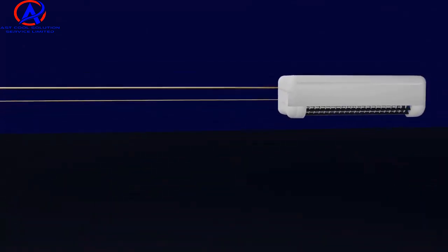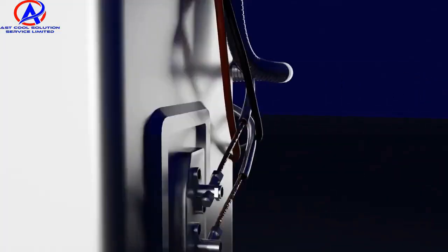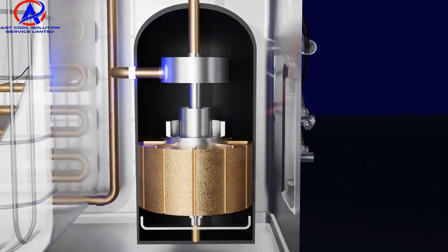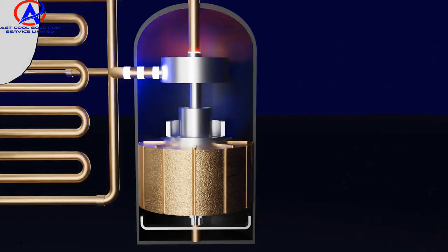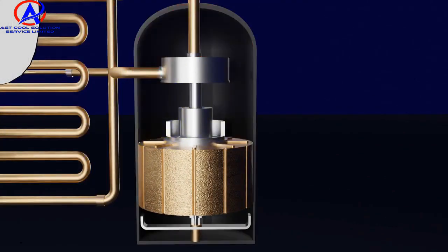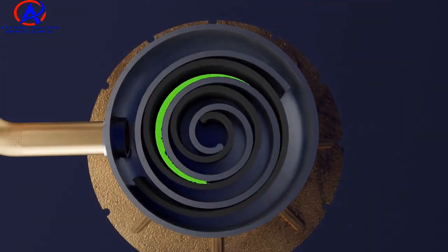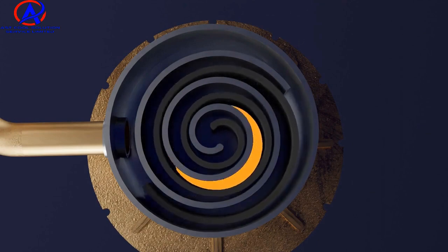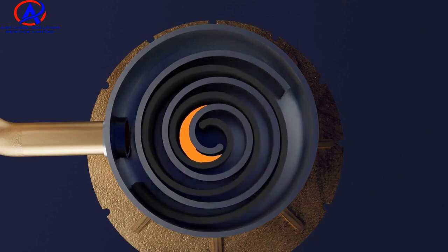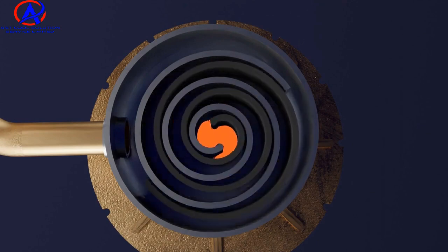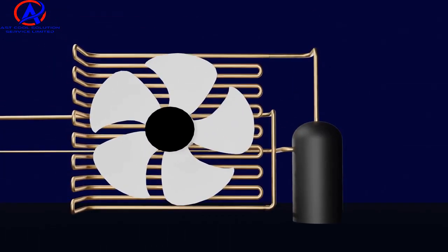At the heart of the system is the compressor. Think of it as the engine that drives the entire cooling process. The compressor pressurizes the refrigerant, transforming it into a high-pressure gas. Here a spiral type of compressor is used. As the gas enters the spiral, space becomes crowded and the gas is compressed. After being compressed, the gas is discharged from the pipe above. This type of compressor is very energy efficient and makes less noise.